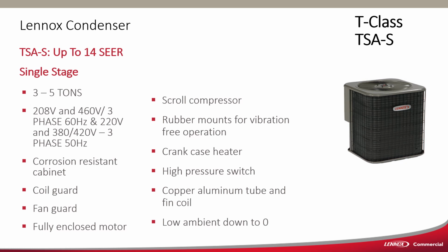It's available in 208 and 460 volt, 3-phase, 60 hertz, as well as 220 volt and 380/420 volt, 3-phase, 50 hertz. It has corrosion resistant cabinet, coil guards, fan guards, fully enclosed motor, scroll compressor, rubber vibration mounts on the compressor, crankcase heater, high pressure switch, copper tube, aluminum fin coil, and is operable to 0 ambient temperature right out of the box. You do not need a low ambient kit.